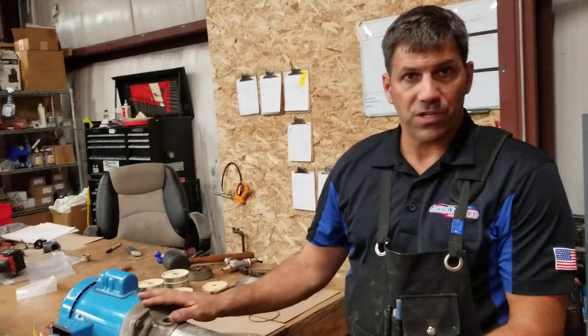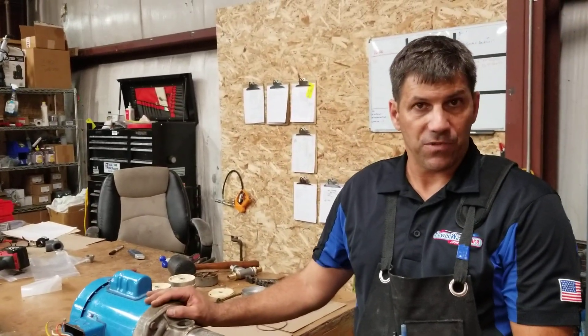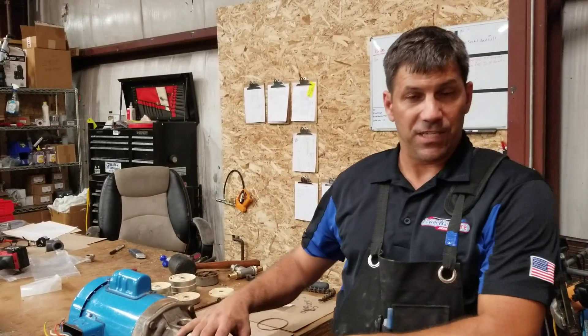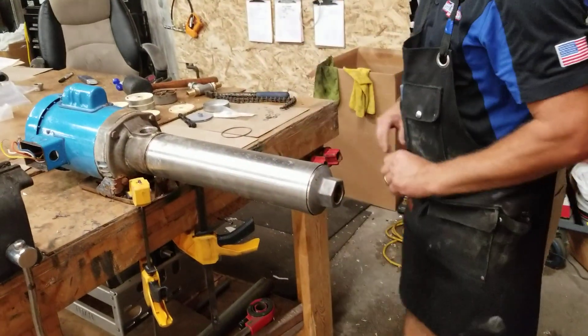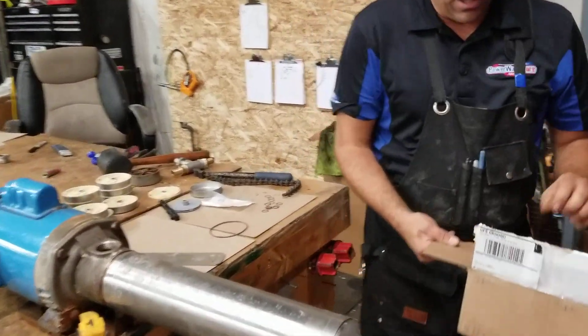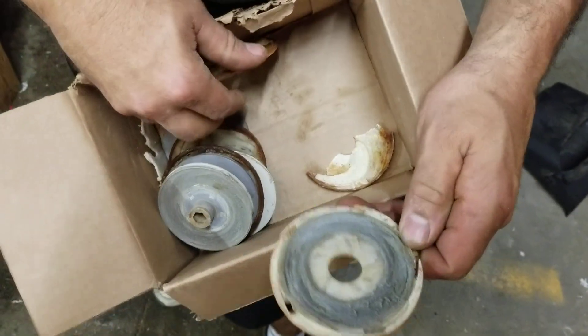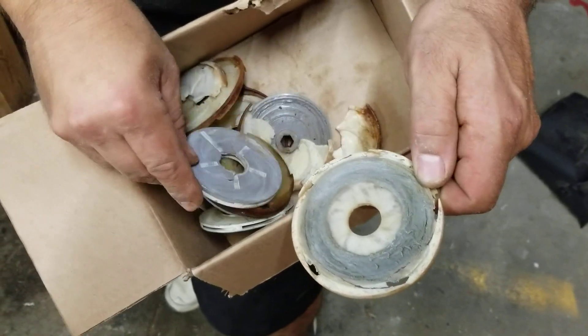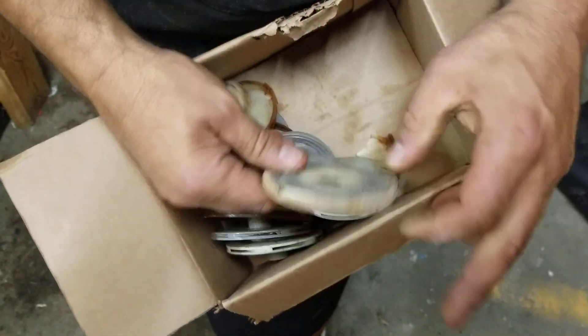This particular pump was sent back to us by a customer who started to try to do the rebuild process himself. The issue he was having is he was able to get the barrel loose but he couldn't get it off the shaft. Here's an example of some of the diffusers and impellers — you can see that this particular diffuser was rubbing so hard on one of the impellers that it actually embedded the plastic in there.